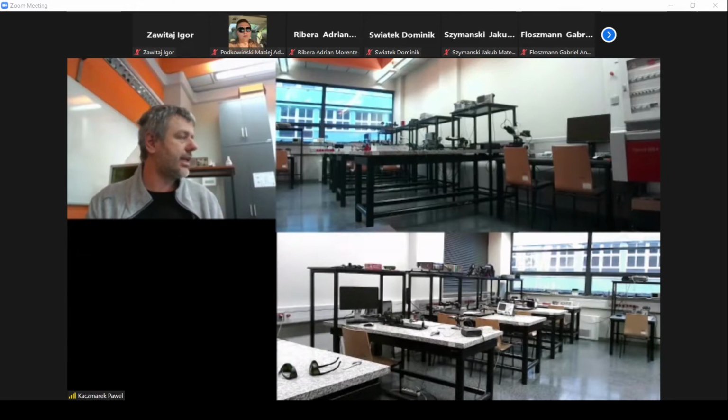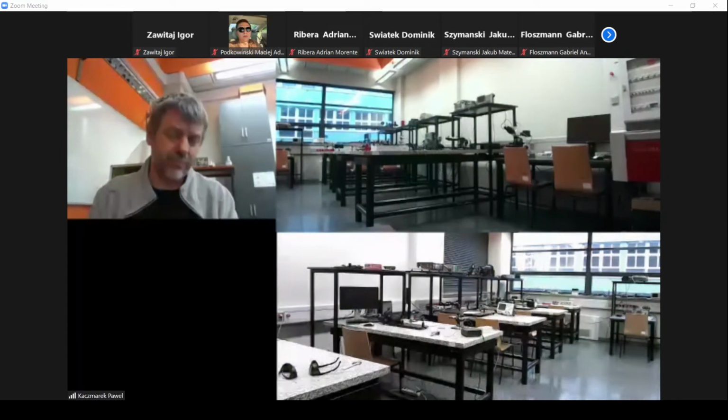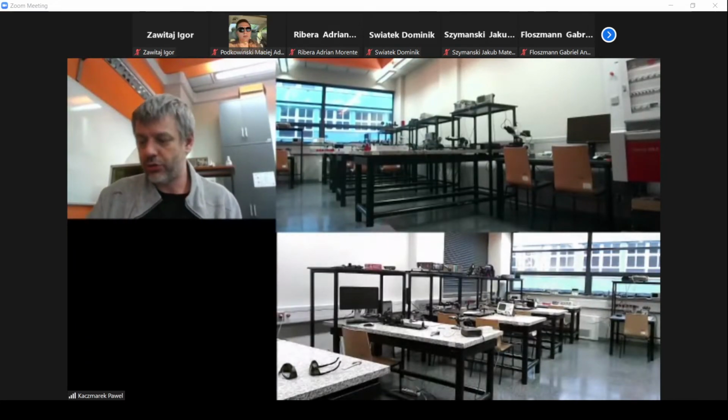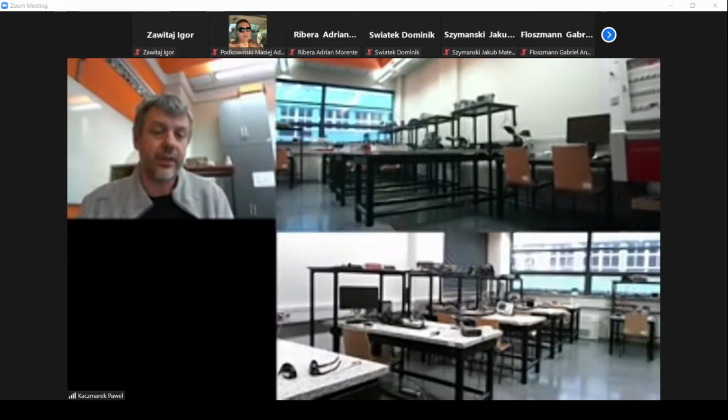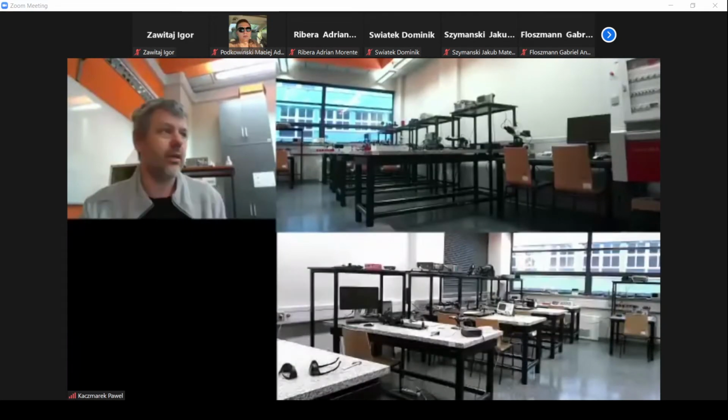Second issue connected with laser safety, especially for the groups who will make helium neon laser experiments. They are gas lasers. These visible lasers here in this laboratory are mostly gas lasers. They are powered by high voltage power sources. So please do not disconnect the laser from the power source, because of the high voltage, which is dangerous, you know why. I don't need to tell you why you shouldn't disconnect the laser from the power source if the laser is supplied by 2.5 kilovolts, for example. It could be quite dangerous, the power supply for such a laser. Not the laser itself, but the power supply could be dangerous.